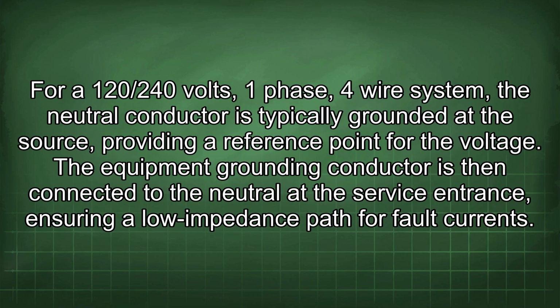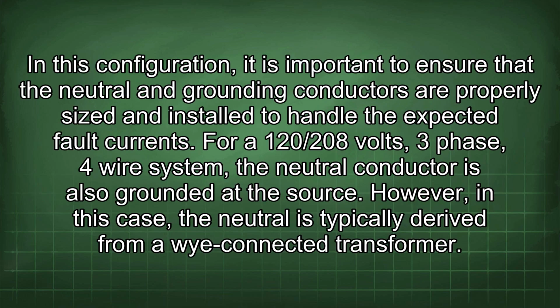For a 120/240 volts, one-phase, 4-wire system, the neutral conductor is typically grounded at the source, providing a reference point for the voltage. The equipment grounding conductor is then connected to the neutral at the service entrance, ensuring a low impedance path for fault currents. In this configuration, it is important to ensure that the neutral and grounding conductors are properly sized and installed to handle the expected fault currents.